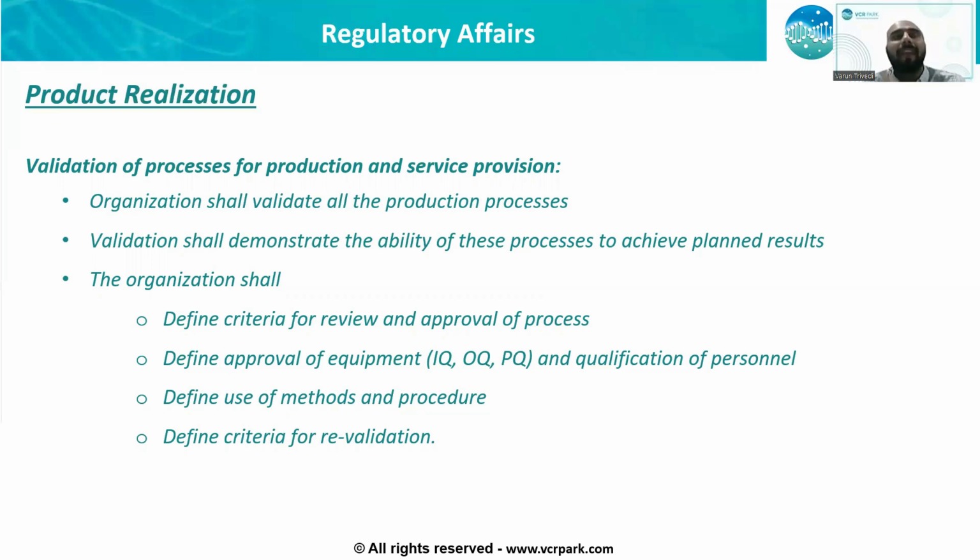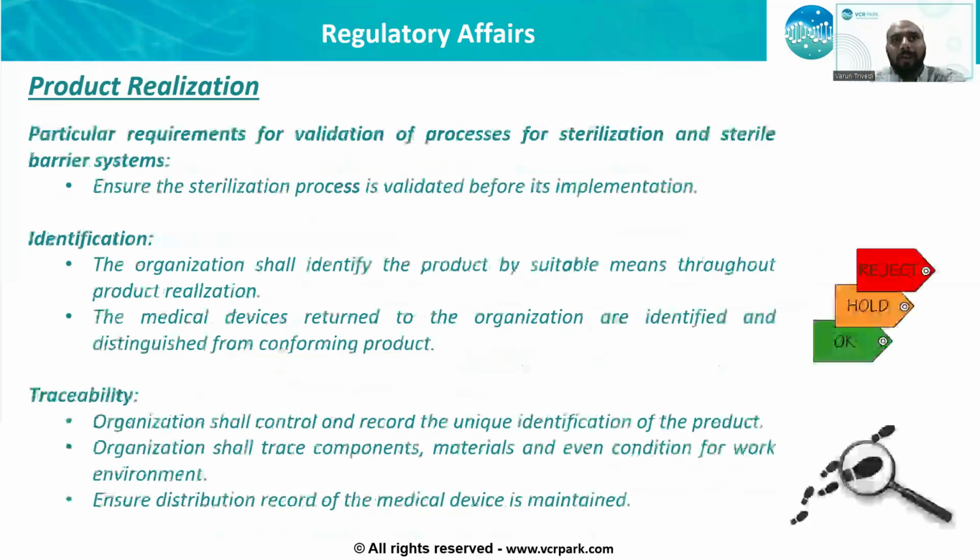And when we run these processes, the final output that we get is what it is supposed to be, shall be maintained and documented. Cases where revalidation is needed, the criteria for revalidation shall also be defined, and at stages where acceptance criteria need to be defined, that shall be captured as part of your overall validation protocol. Validation for sterile barrier systems shall also be defined similarly, and special emphasis shall be given to them because these will be seen as special processes.